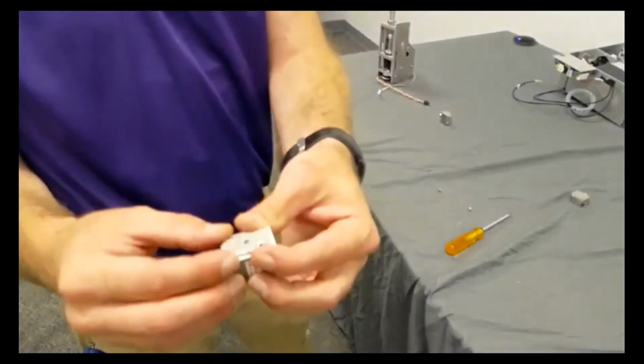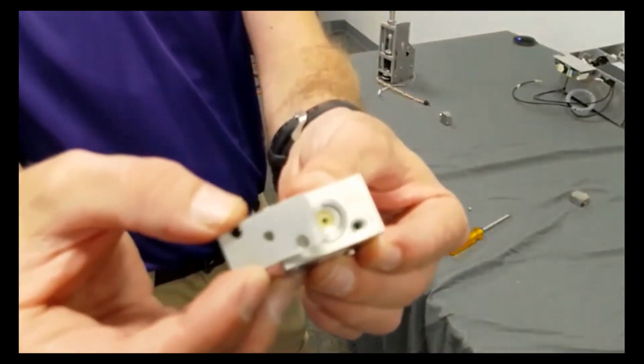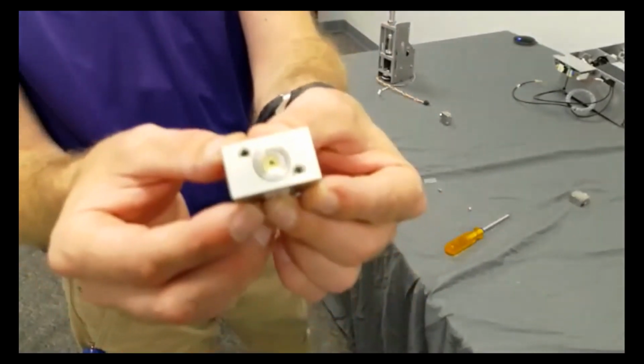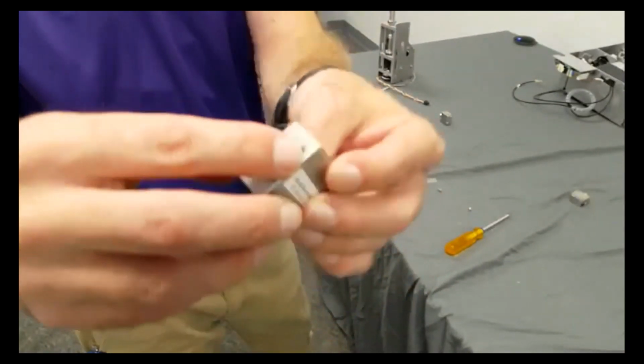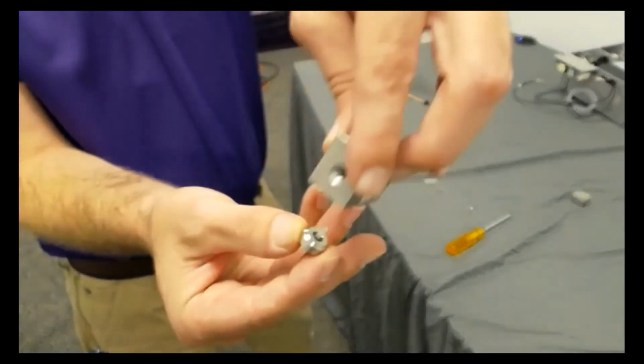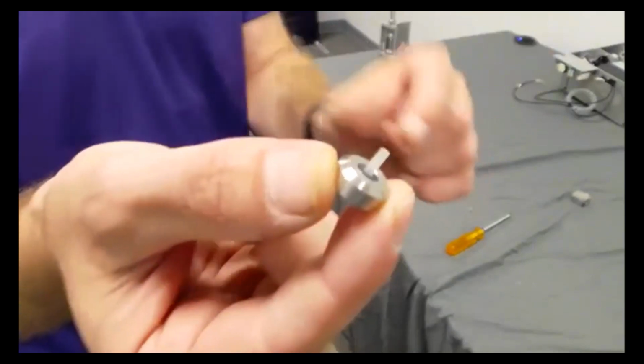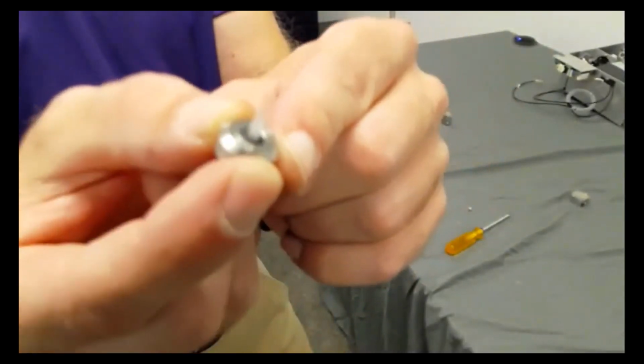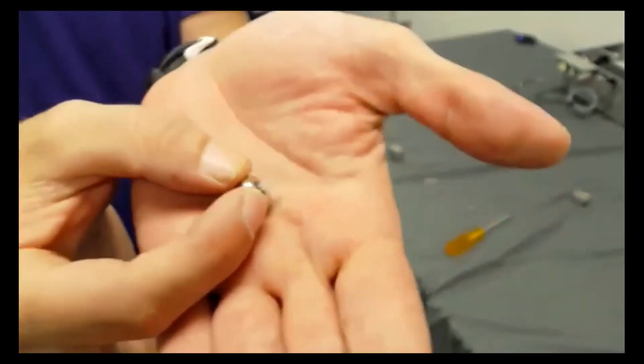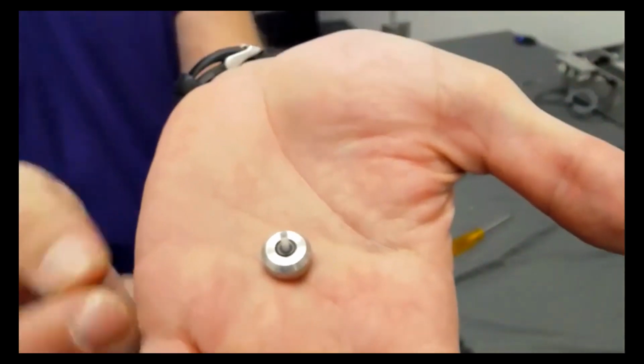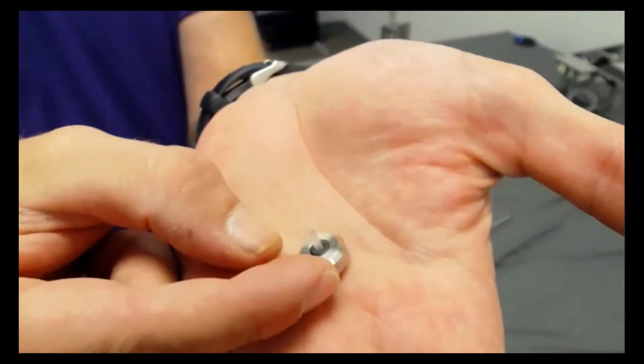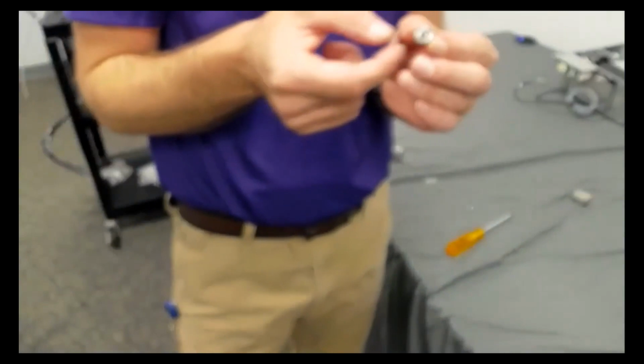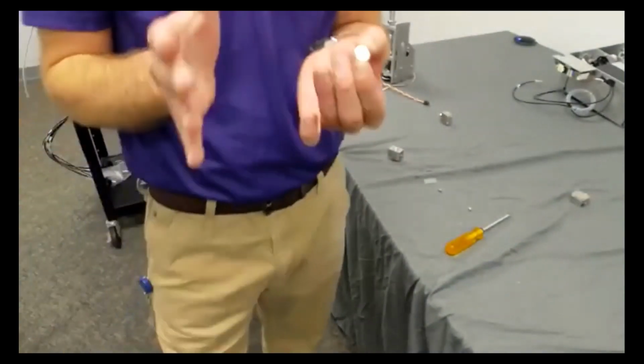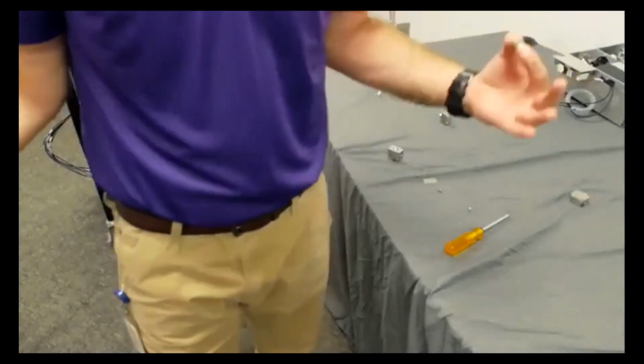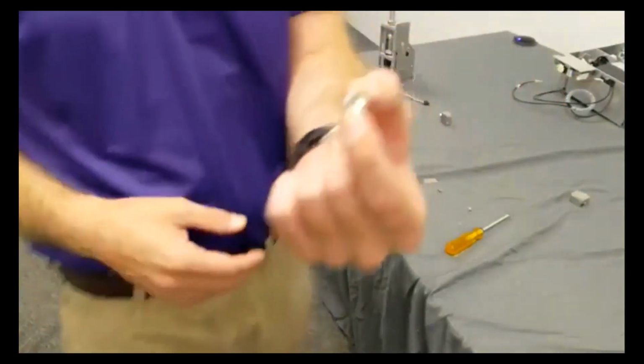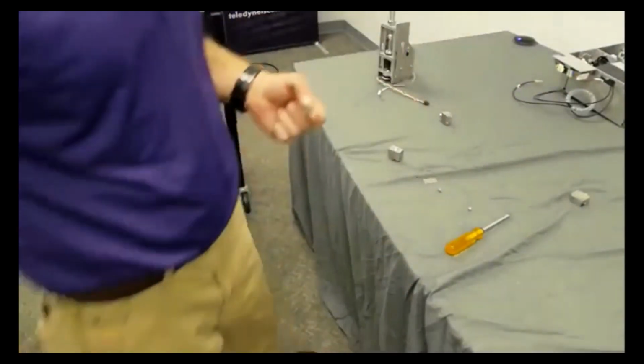So now I've got those screws out so I can take this plate off. And what you see here is that's actually a quartz rod that's mounted in. That should come right out. Ooh, super cool, super cool. So that's a quartz rod. You'll see it better. It's very small. So when you get these out, if you've got a flow cell that just won't clean with acetone, methanol, DMSO, whatever solvents you're using from the table to flush out the flow cell, you can take it apart.